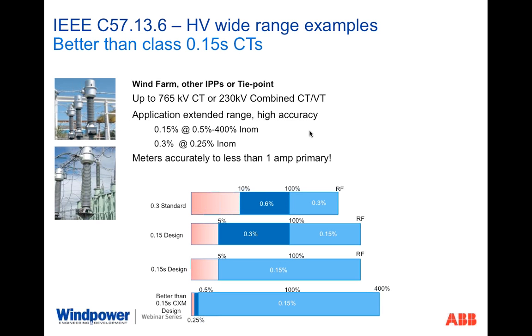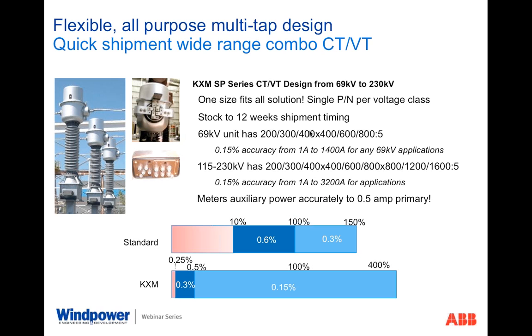Now, we've been talking primarily about CTs, but one of the things I wanted to mention about the combos, the combination metering units, is that they are also being used heavily in wind farm development. In fact, if I would say there is a standard, it is to use the combined CT-VTs in installations to save space, so you save cost on the installation, plus combine it with a high accuracy, wide range performance. And so those have been really popular with developers to save a lot of cash in terms of your total installed cost.